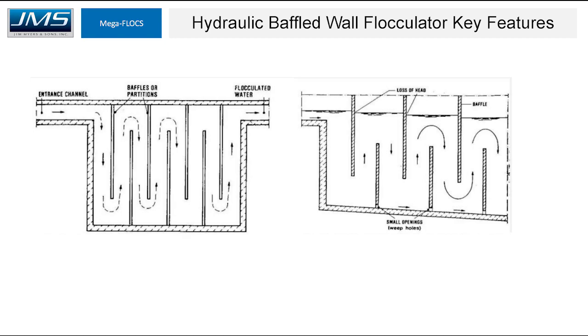The hydraulic baffled wall flocculators, also known as baffled channel flocculators or Alabama flocculators, consist of numerous walls with specific spacing to create the appropriate velocity gradient. The only way to adjust velocity gradient is by adjusting the flow. These walls can be made of concrete, wood, fiberglass, or stainless steel, and you can do a serpentine flow or over-under flow.